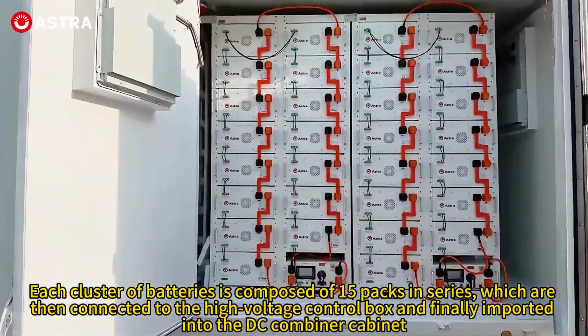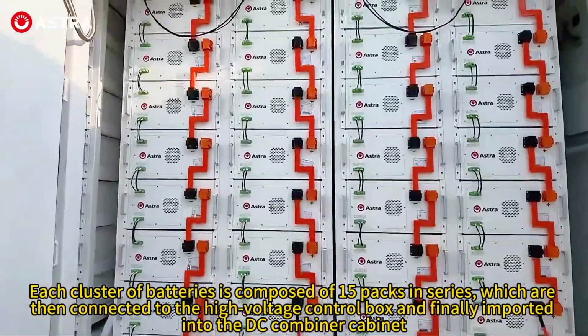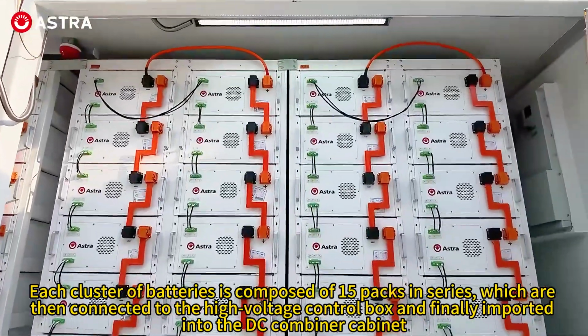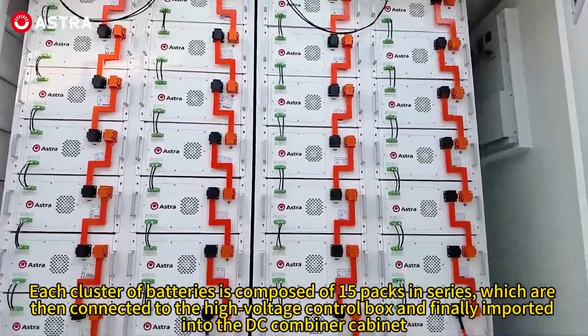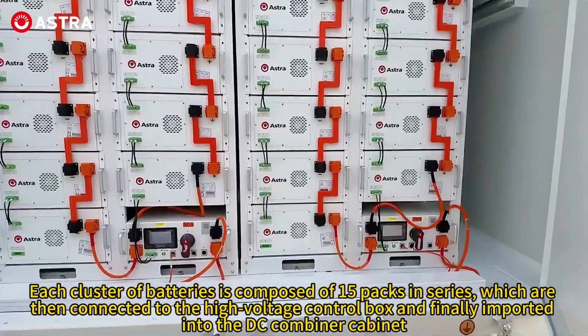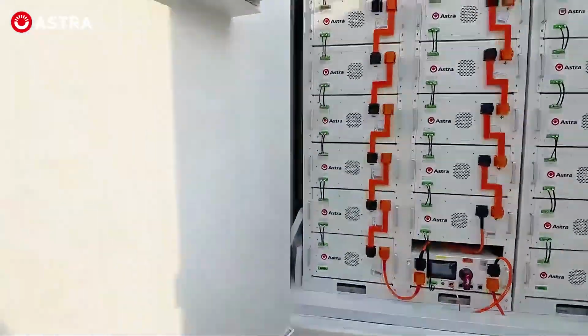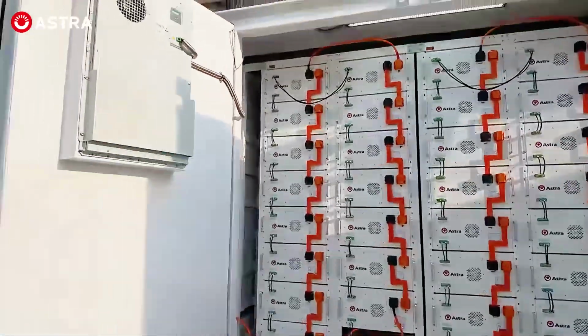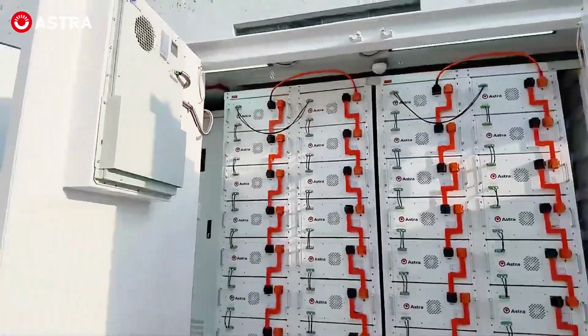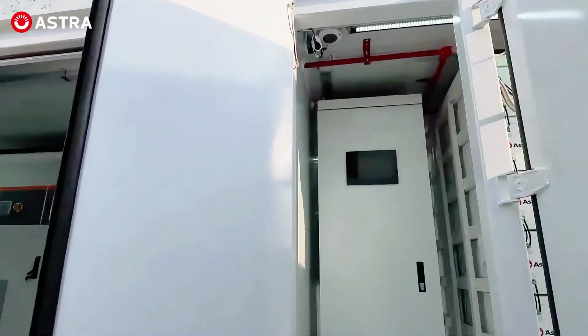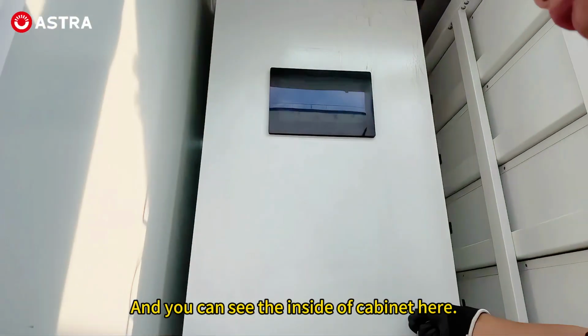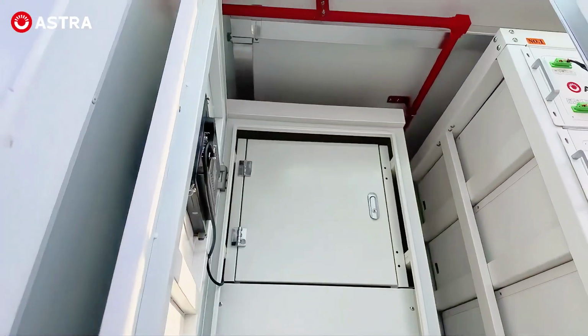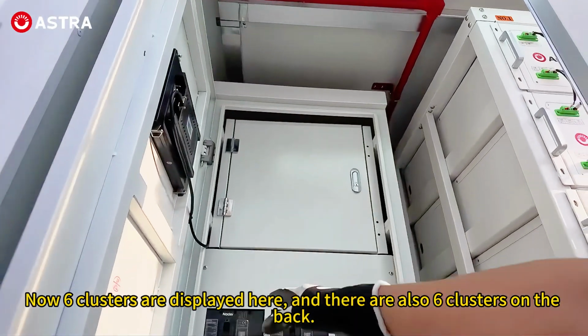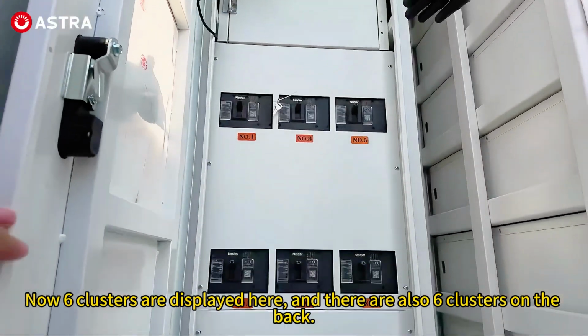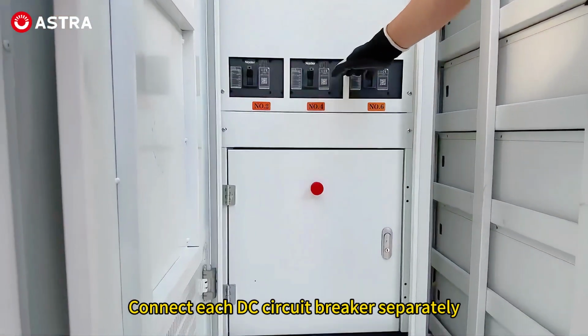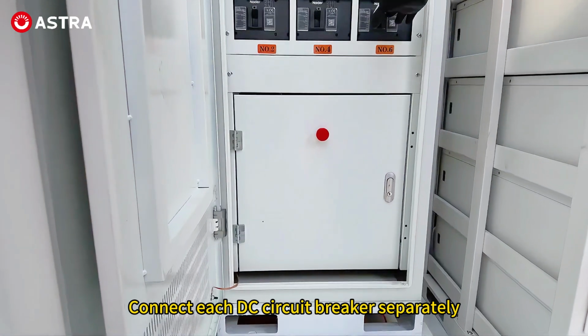Each cluster of batteries is composed of 15 packs in series, which are then connected to the high-voltage control box, and finally imported into the DC combiner cabinet. And you can see the inside of cabinet here. Now 6 clusters are displayed here. And there are also 6 clusters on the back. Connect each DC circuit breaker separately.